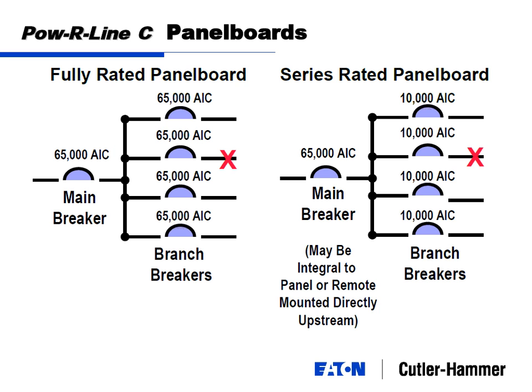And UL has got some requirements, and I don't know those off the top of my head, but it ties to, I think, the magnitude of the fault, where it says you can put it twice or 3 times. But obviously, the life of the circuit breaker is going to depend on how many faults and the magnitude of faults it sees. So no matter which circuit breaker you have, if every day it trips on overload, your circuit breaker is going to wear out over, let's say, a year.